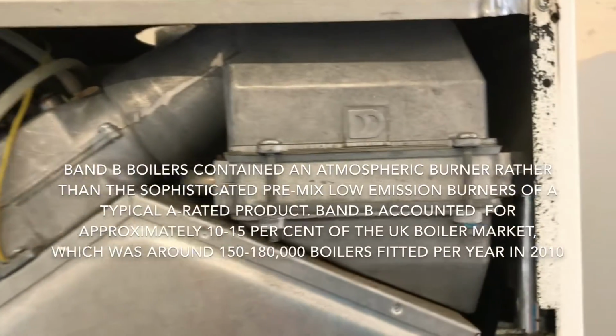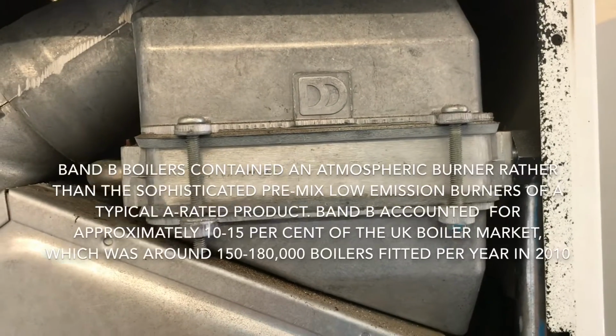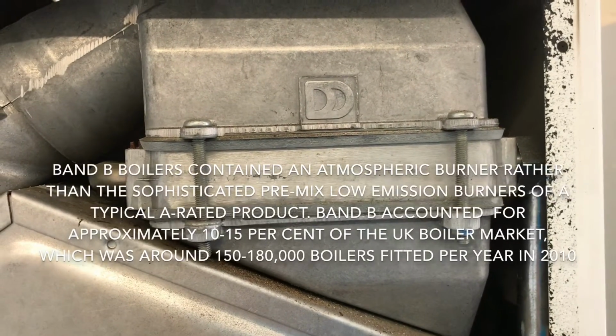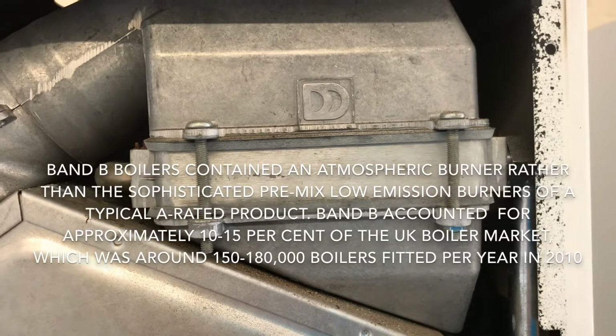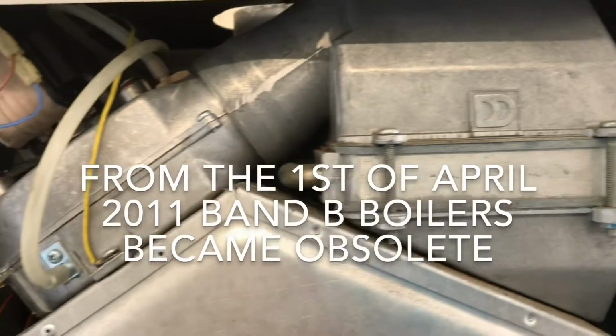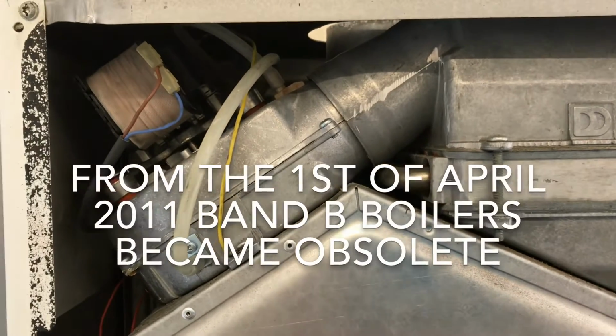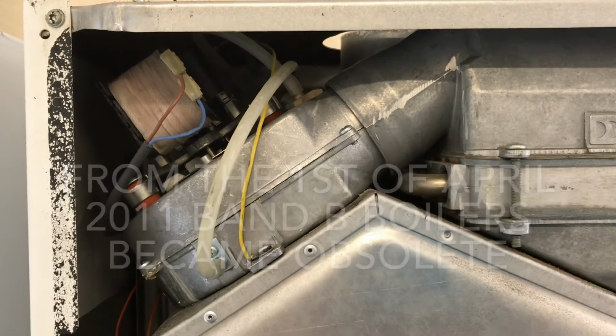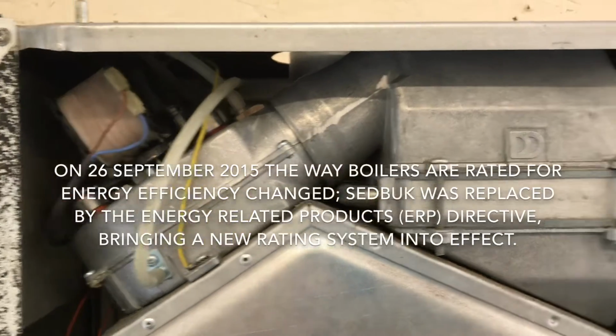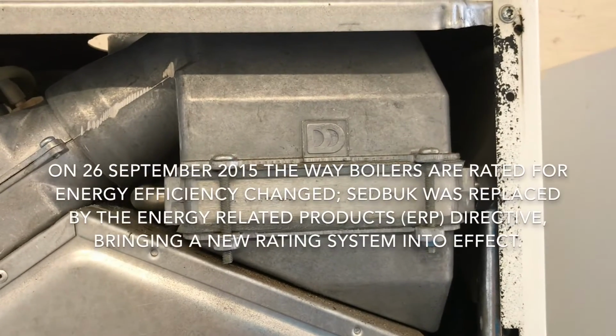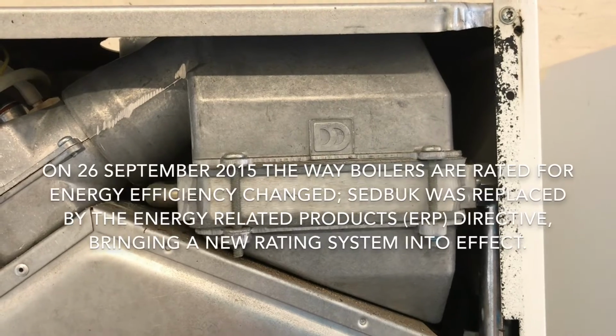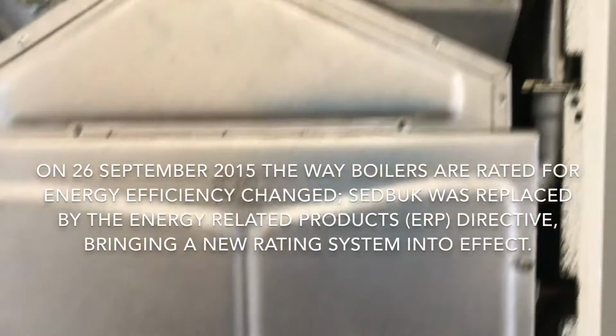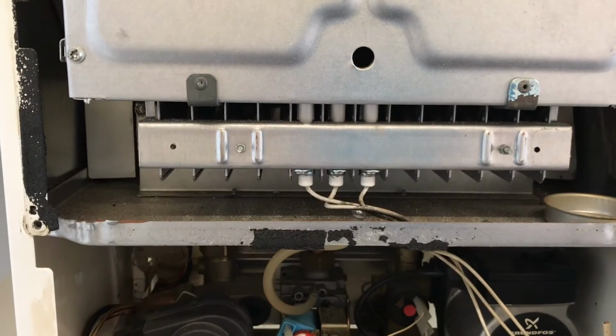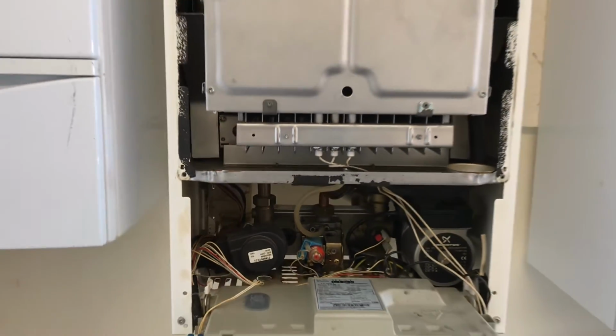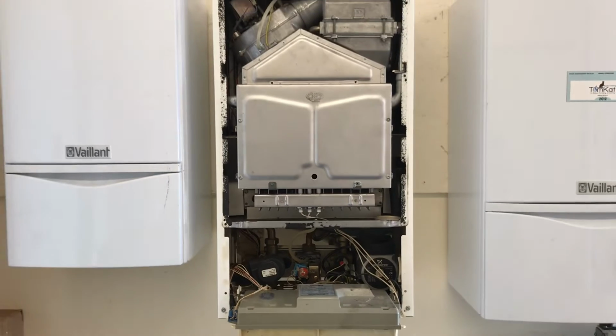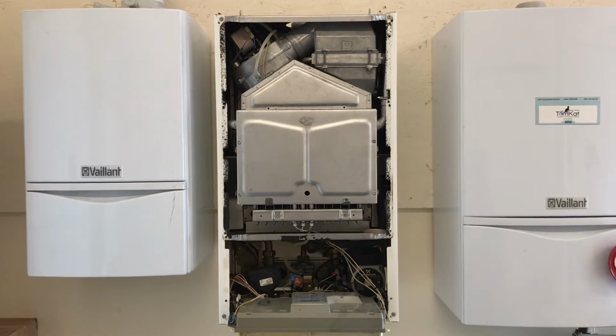What we're looking at here now is a secondary heat exchanger. This is where the return pipe would come back in to the boiler and then be heated by the flue temperatures exiting. This boiler would exit its flue temperatures at about 150 degrees, and this secondary heat exchanger would take that heat out and preheat the return water so the burner would have less work to do. So this is an atmospheric boiler, but this is what we call a band B boiler.